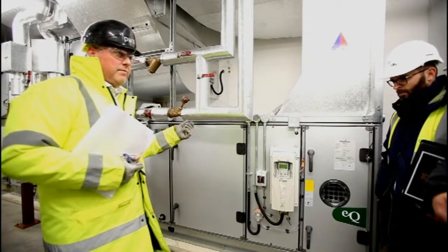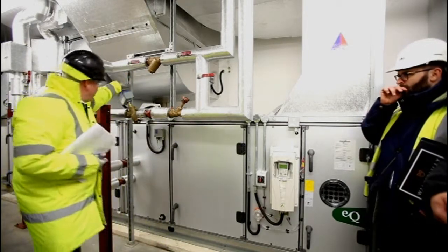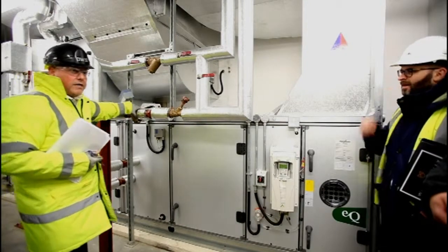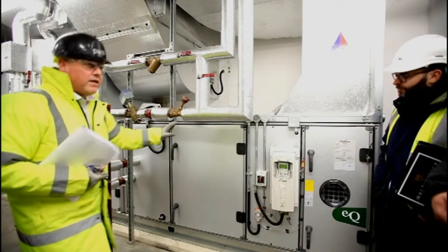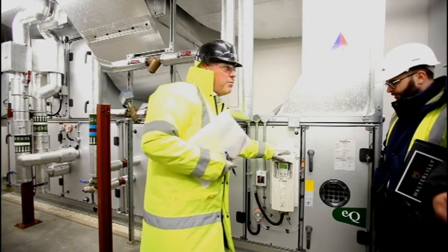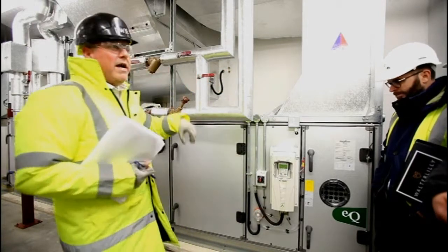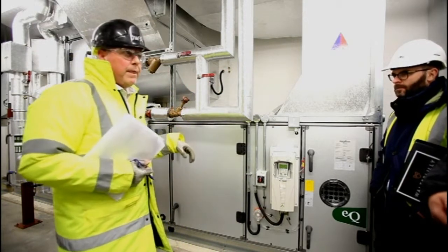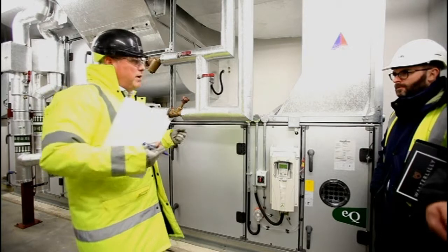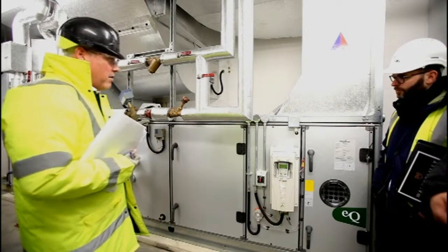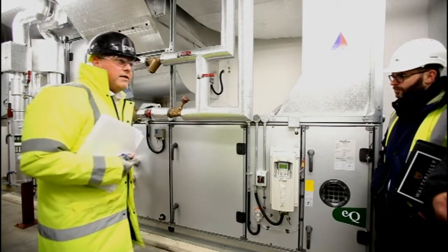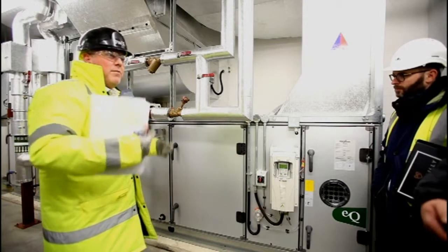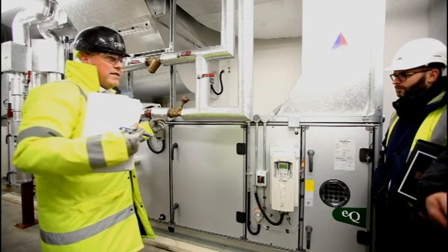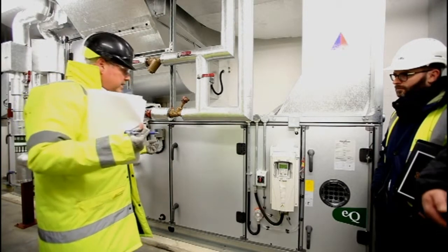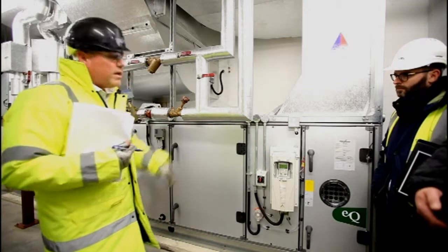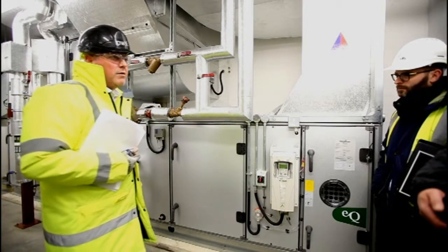Then should the temperature decrease and we need more heat in the building, two things will happen. The valve will open up and create more heat through into the heating coil. The fans will increase in speed to get warm air into the space quicker. So when we come to reheat the building, you'll probably find that the fan will be on full, blasting away to try and maintain the temperature within that space. Once we maintain the temperature, the humidity and the CO levels within the area, these will ramp down to just a small trickle.